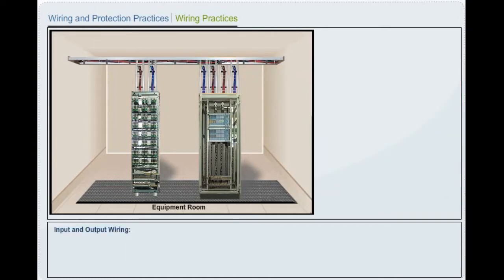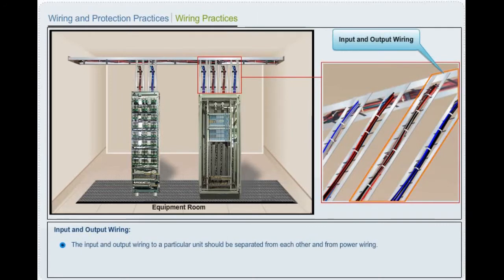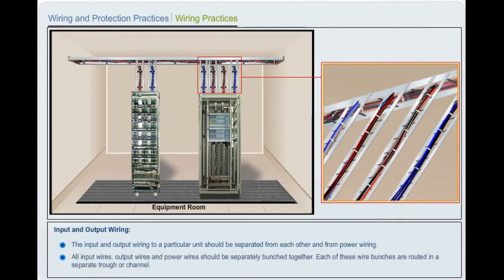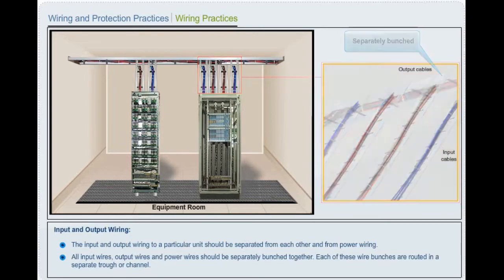Input and output wiring. The input and output wiring to a particular unit should be separated from each other and from the power wiring. All input wires, output wires, and power wires should be separately bunched together. Each of these wire bunches are routed in a separate trough or channel.